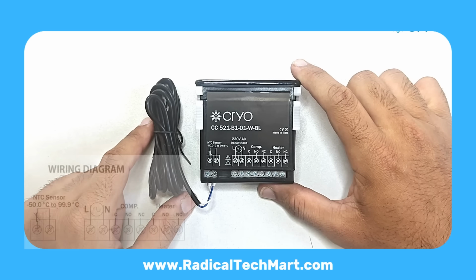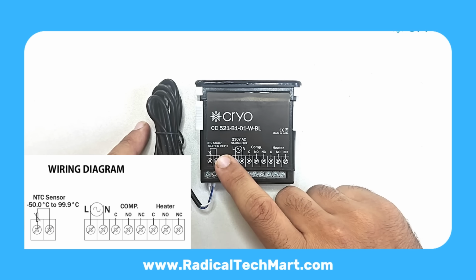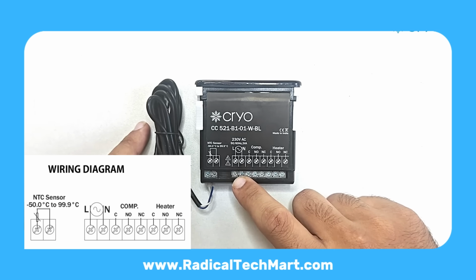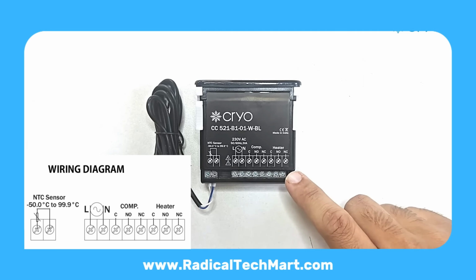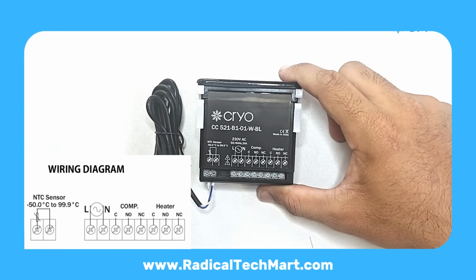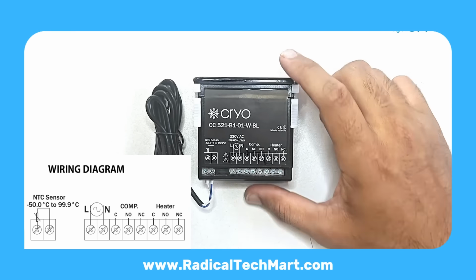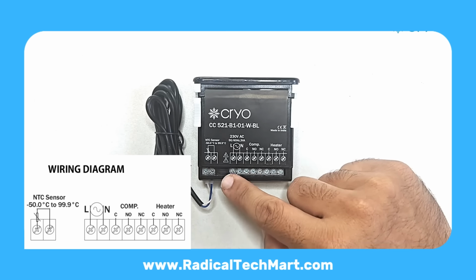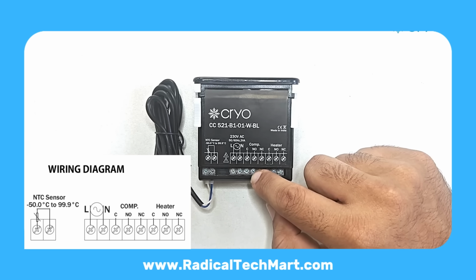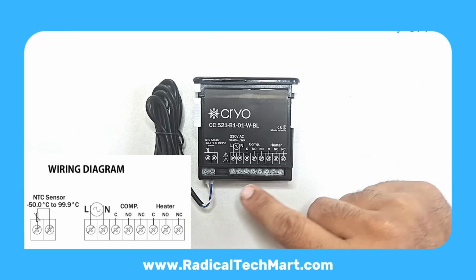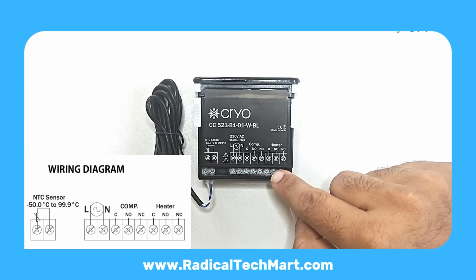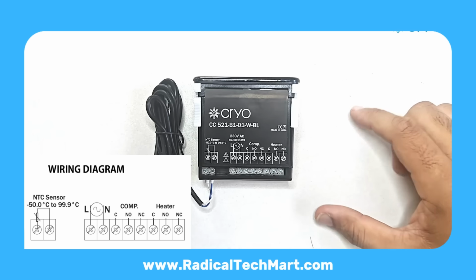On this controller, you'll find terminals for line, L, and neutral, N, power supply. You also get two relay outputs, one for your compressor and one for your heater. That means you can use it for both cooling and heating control in a single air dryer system. Before we go into settings, let's first look at the wiring connections.